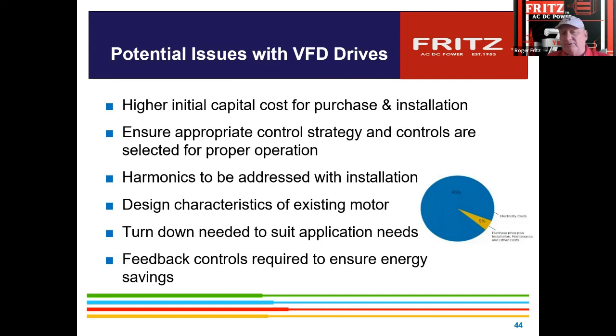Ensuring the proper control strategy, so that they get installed, they get properly controlled to a sensor and or BMS system. We work hand in hand, both with the building management systems, and we work hand in hand with the controls. And at the end of the day, they can operate on their own. You got a pump running on pressure regulation. It can all sit there and operate without even having to be tied to a BMS system and still save the same amount of money.